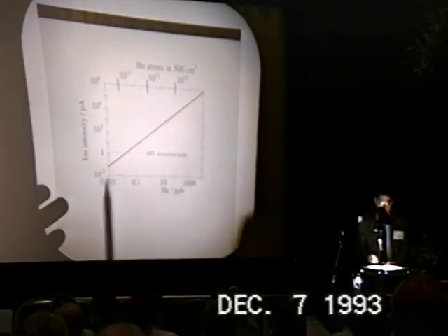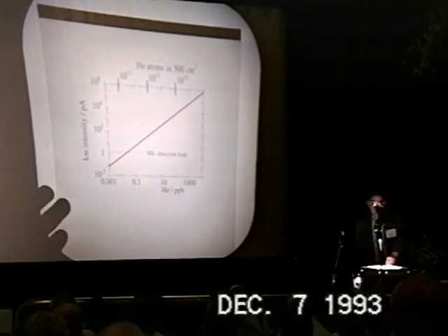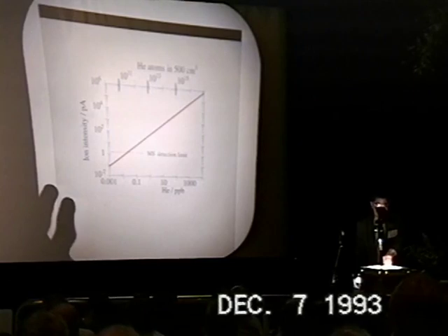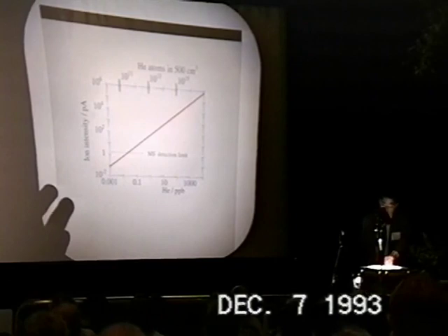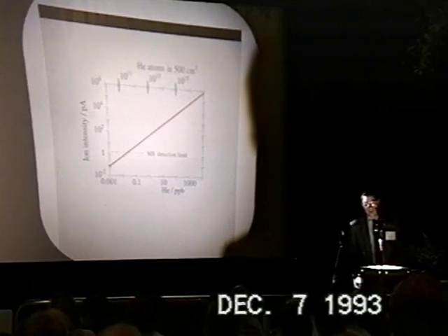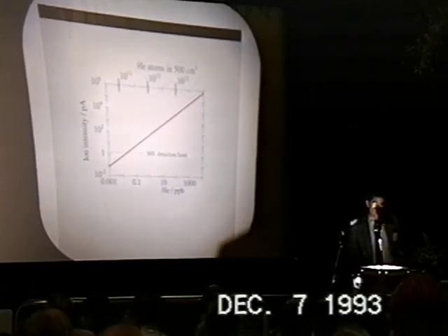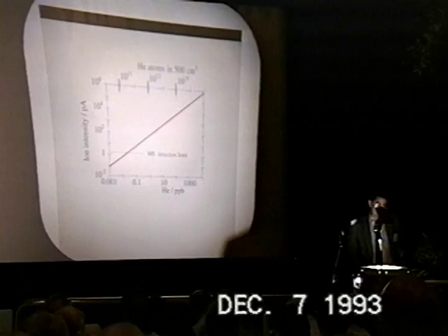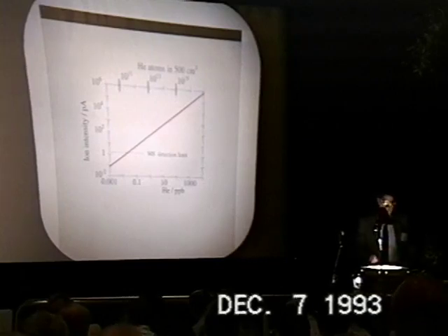one can draw this red line, which is our detection limit. Actually, in the actual condition of the experiment, the mass spectrometer had a high intensity detection limit of about 1 picoampere, which is not the sensitivity, the limit of the mass spectrometer itself in that particular condition.